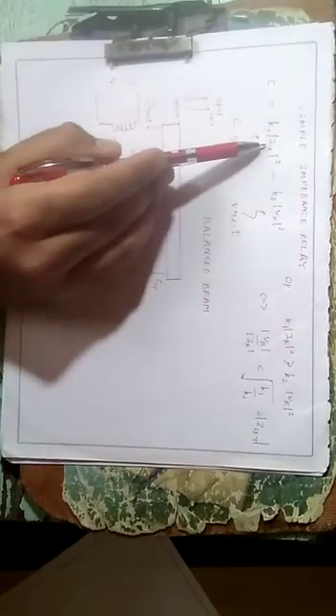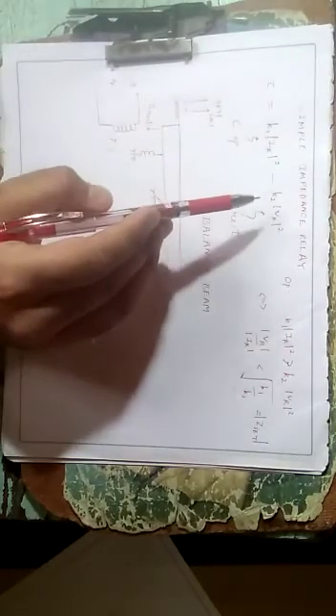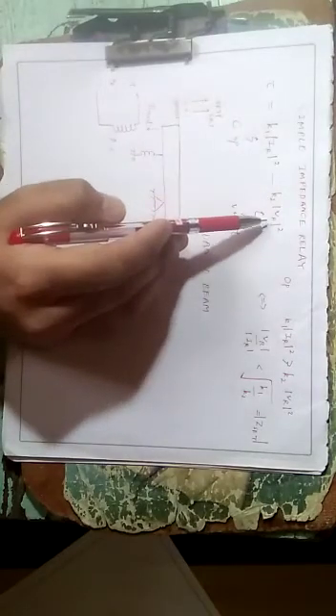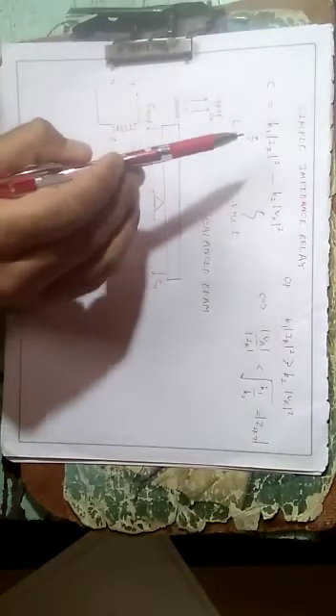The torque is proportional to the current square, minus some constant times voltage square. There is another term which I have not written here, that is because of the restraining spring, but typically it's very small, especially under fault conditions. So let us try to interpret this equation. What does this equation mean?